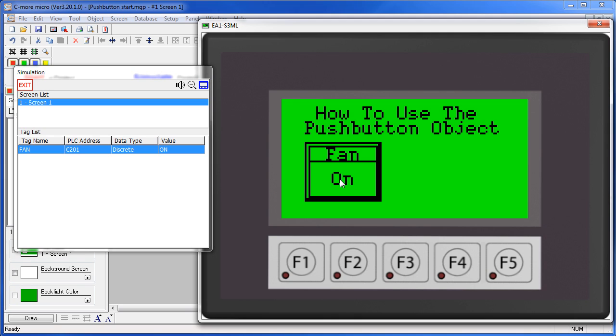This is a really great option when you want the PLC to be in control of the switch action. For example, using this SET ON switch, the user can enable the process like we just did here, but he can't re-enable the process until the PLC resets the tag.